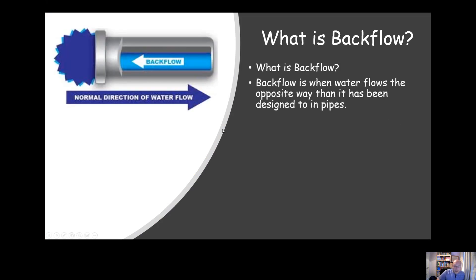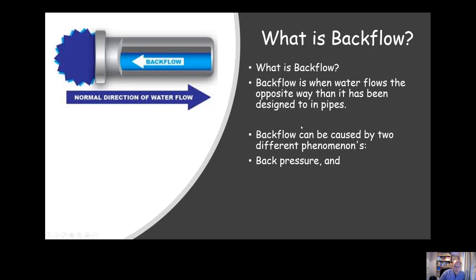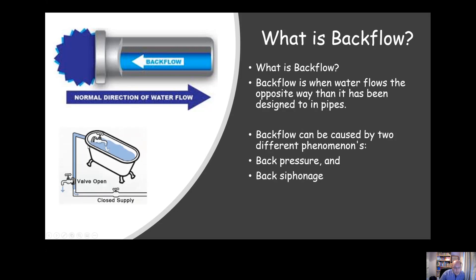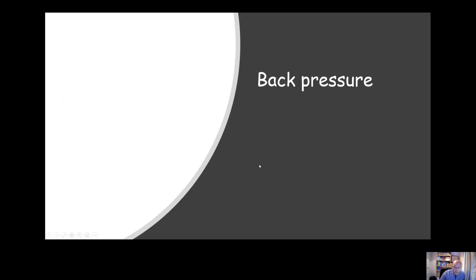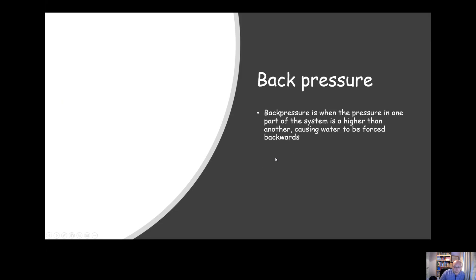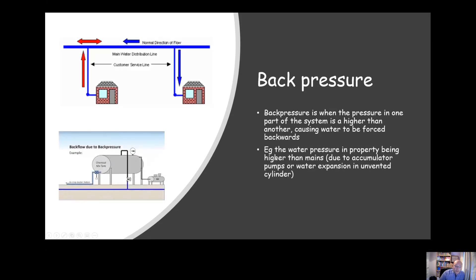So firstly, what is backflow? Backflow is essentially when water flows the opposite way than it's designed to in the pipes. It can be caused by two different phenomena: back pressure and back siphonage. The example on the left shows back siphonage — we'll chat through that in a bit more detail in a second. Back pressure is when the pressure in one part of the system is higher than another, forcing water back the opposite way than it's been designed.